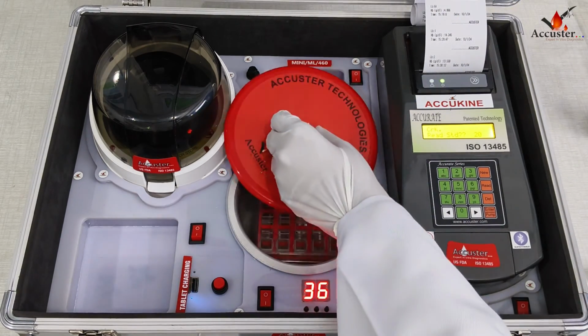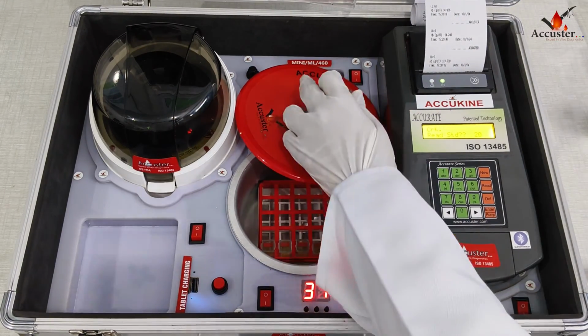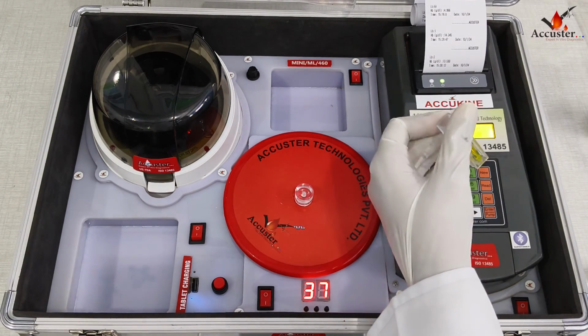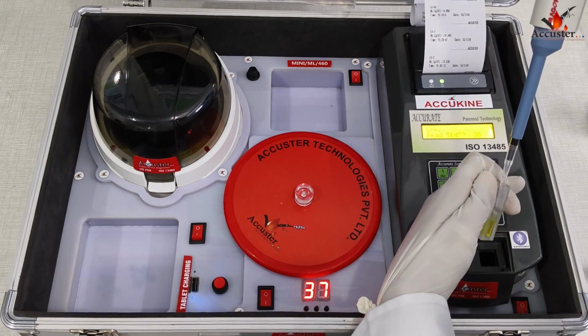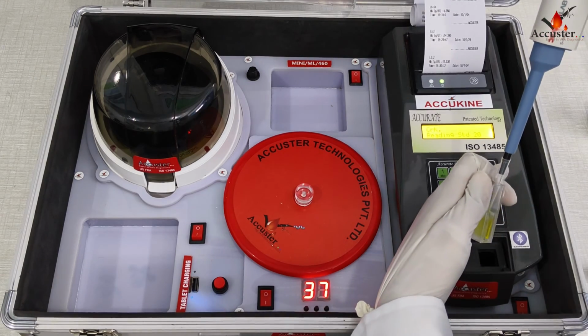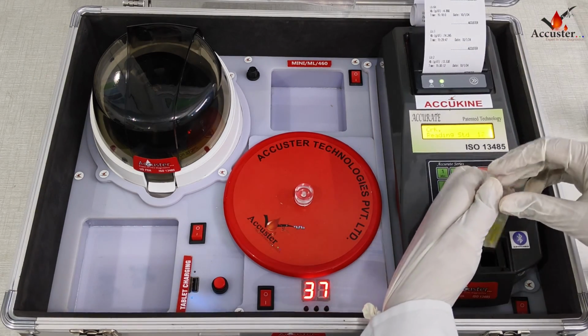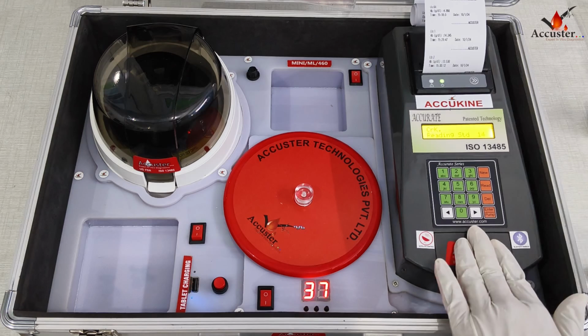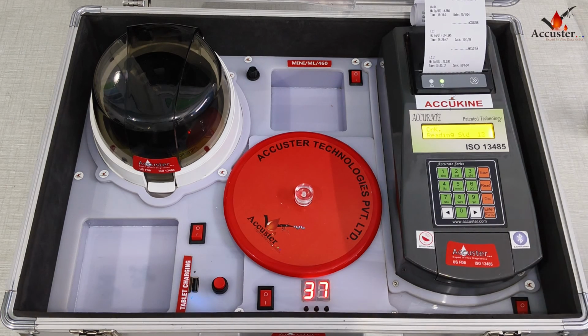Take the 1 cuvette with reagent out of the incubator and mix 50 microliters of standard with the help of a micropipette and press enter while mixing the standard. Then insert the cuvettes in the analyzer. It will take 80 seconds for the reading to display.